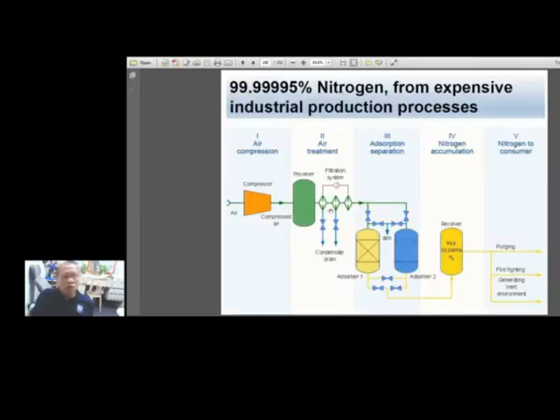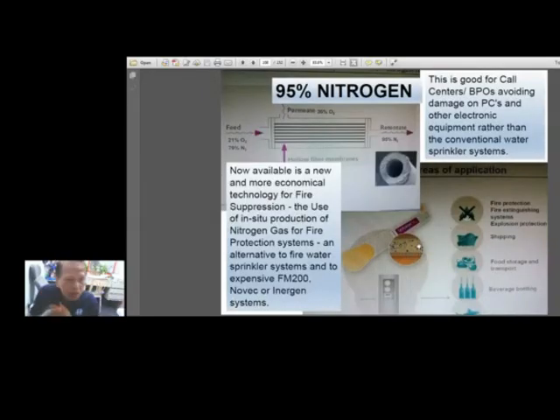It's a means of processing, no? So it is a system that produces nitrogen from air. So take note here, you have air compression, then air treatment, then you have adsorption, separation, and then here now you have nitrogen accumulation, and then the nitrogen is injected to your switchgear or equipment. So this system produces 95% nitrogen.